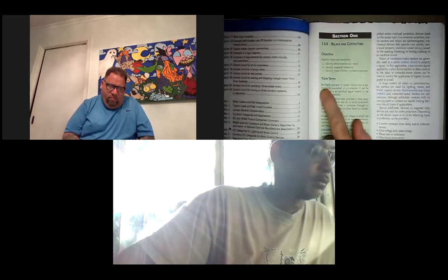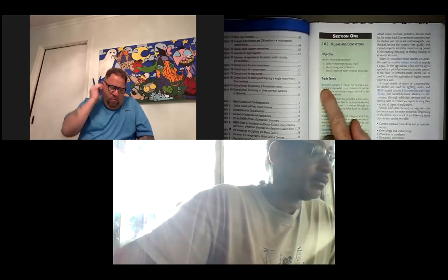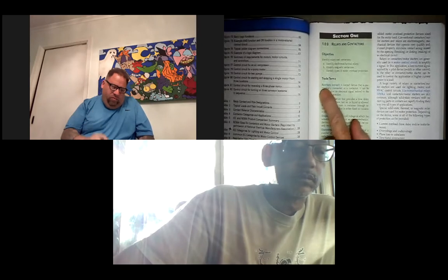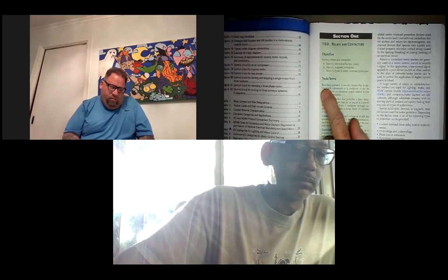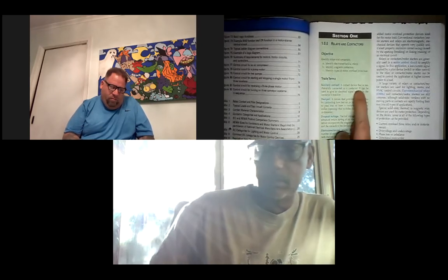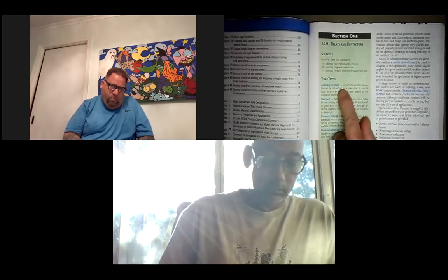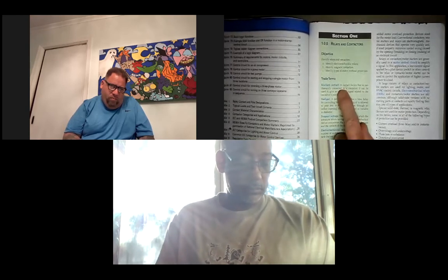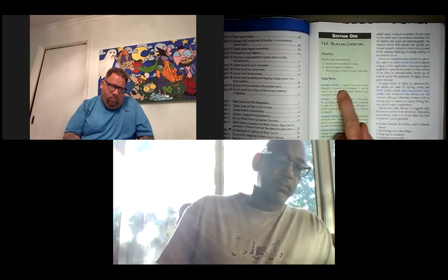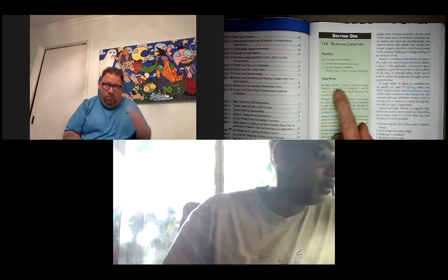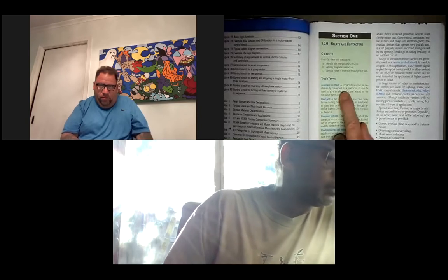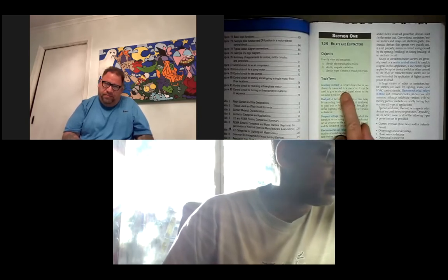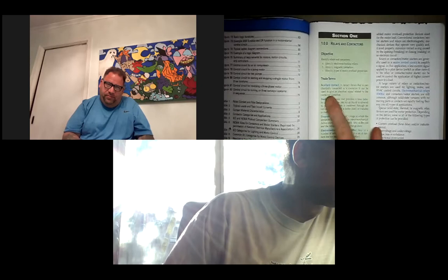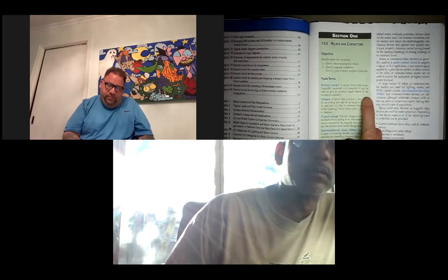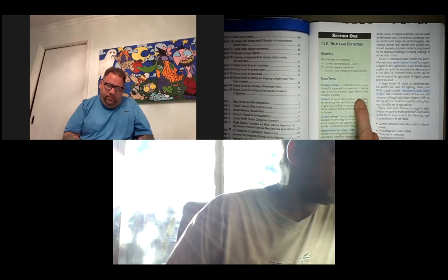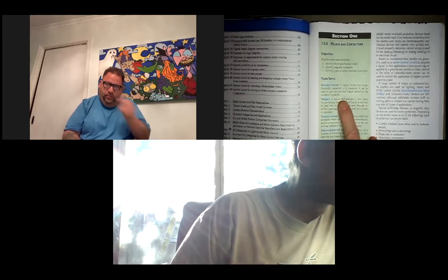Auxiliary contact. An auxiliary contact is an extra contact. It's usually mounted on the outside of a contactor or a motor starter. You'll have 4 main contacts, 3 for the 3-phase motor and 1 as a holding contact. And then outside of the frame, you can snap on aftermarket contacts, and those are the auxiliaries. A contact device that's mechanically connected to a contactor can be used to give an electrical signal related to the contactor's position.